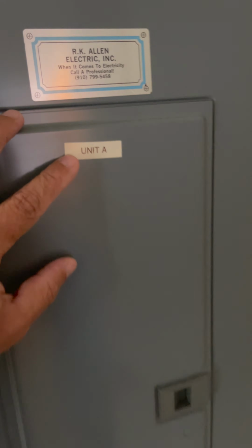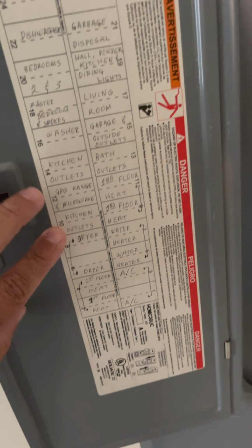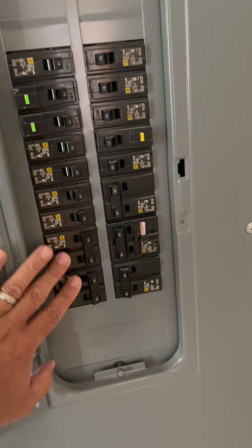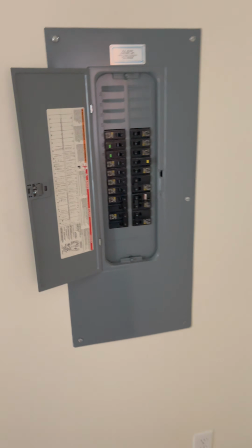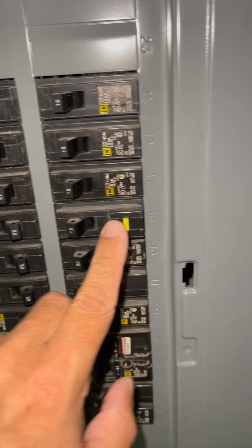Okay, so I've got my bearings of what I need to inspect. I'll go back down and start with some systems that I can find. It'd be really great to find an electrical panel and a hot water tank and the 2 units. So I found the electrical panel in the bedroom. The breakers are all labeled. That's really nice. And I've got AFCIs and GFCIs. The panel is secured to the wall, and it's located in this bedroom.